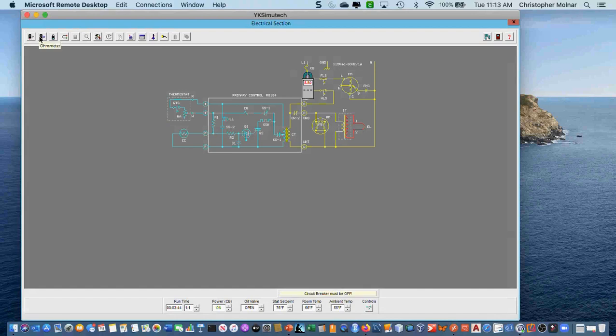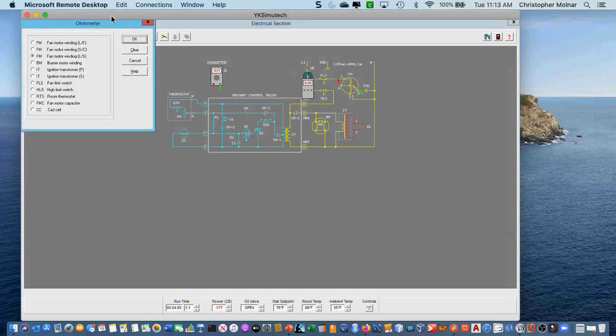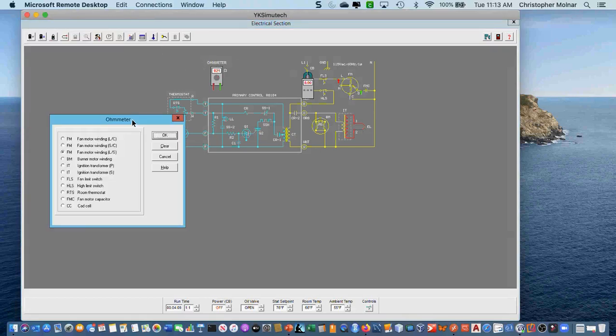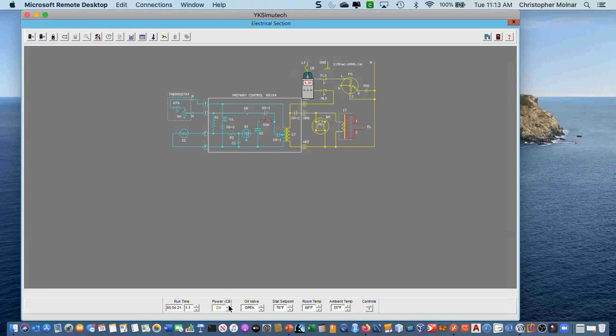To take an ohm reading, I cannot use the ohm meter with the circuit breaker on. I have to turn power off. Then I can use an ohm meter. Let's say I wanted to ohm out the blower motor. Okay, I can ohm the blower motor. So I can take a number of ohm readings, and I can always see where my ohm readings are by clicking on the meter and getting the different spots. Okay, and I can get rid of the meters by just clicking clear and OK, and then I can turn my power back on. You cannot have power on using the ohm meter. It's part of basic diagnostic skills.